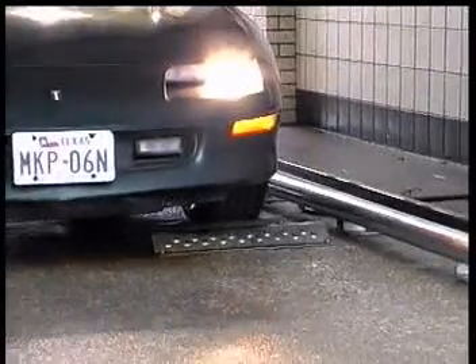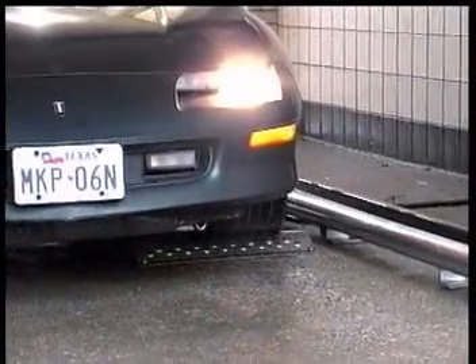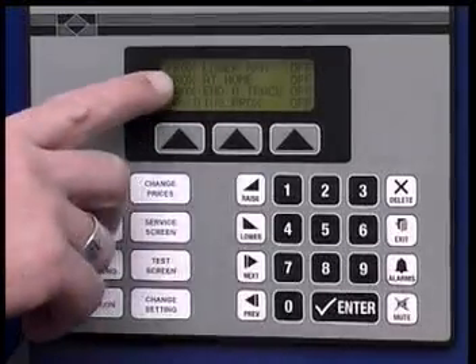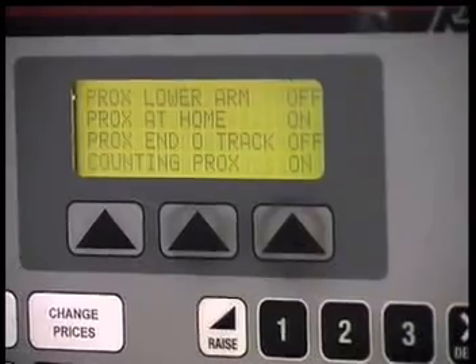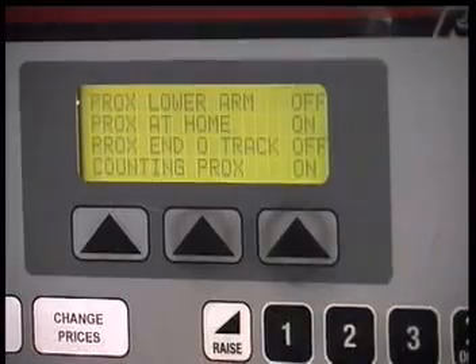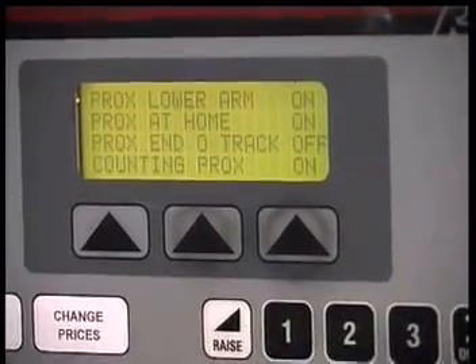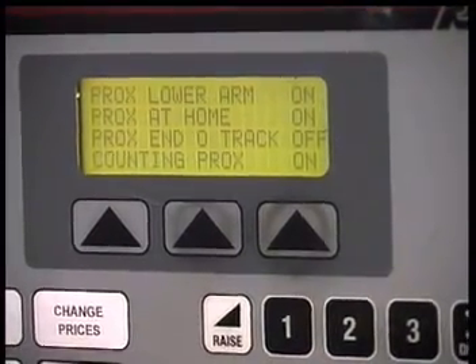The program looks at this prox during the first 1 second of the wash cycle to see if the lower prox is off in its at-home position. If the lower prox is on, this fault message is displayed and the entrance controller is disabled.